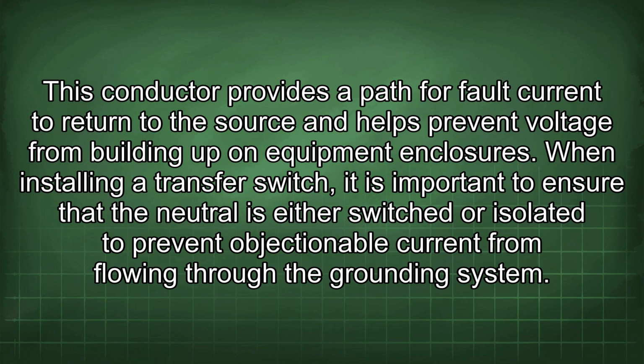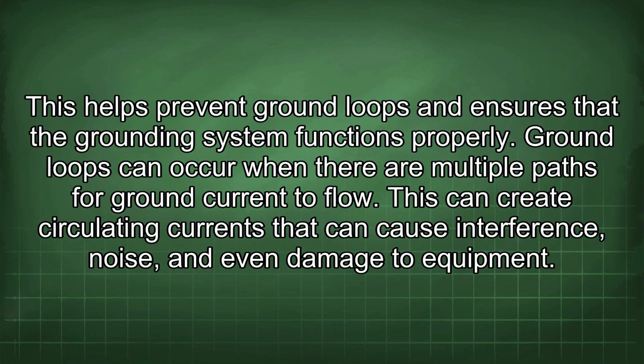on equipment enclosures. When installing a transfer switch, it is important to ensure that the neutral is either switched or isolated to prevent objectionable current from flowing through the grounding system. This helps prevent ground loops and ensures that the grounding system functions properly.